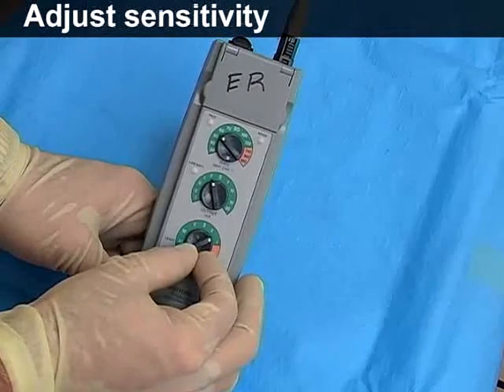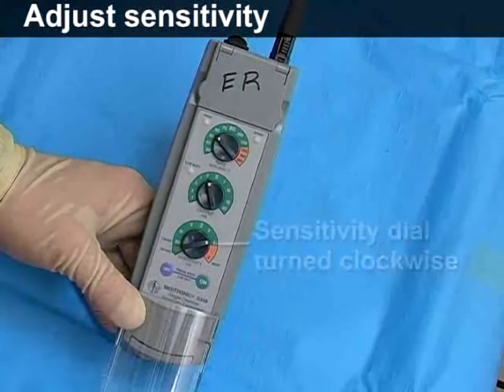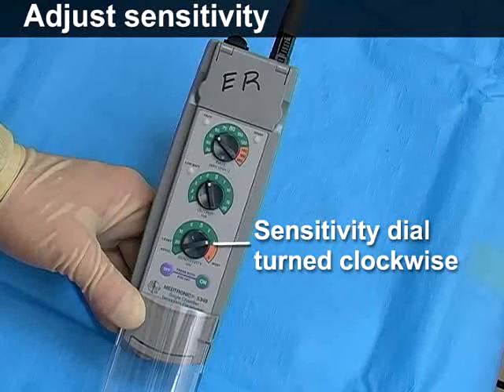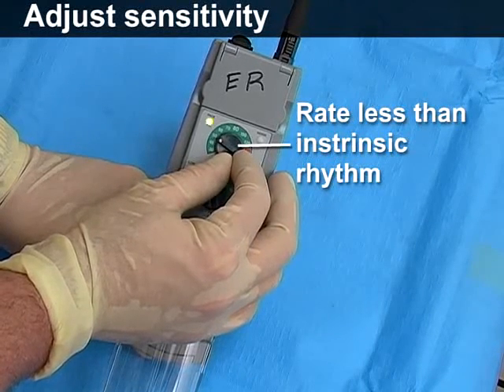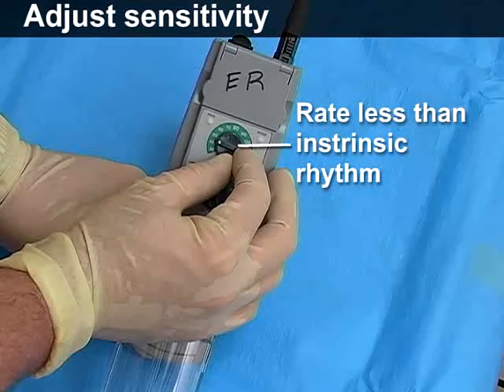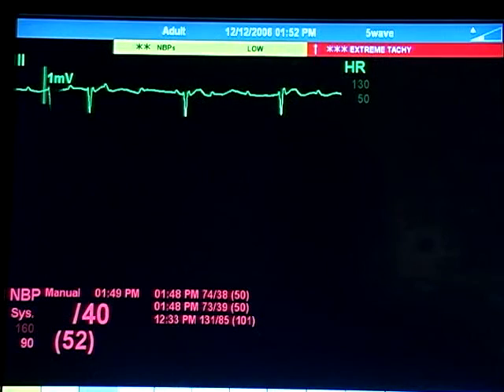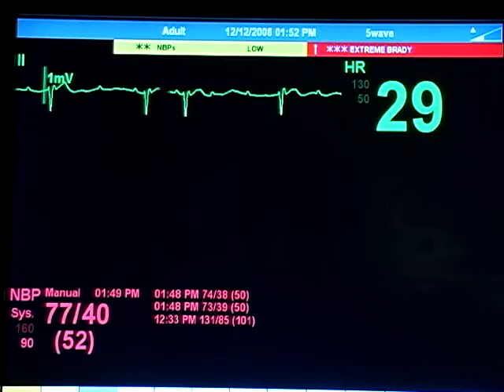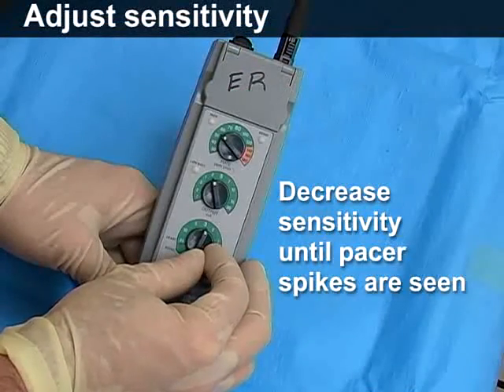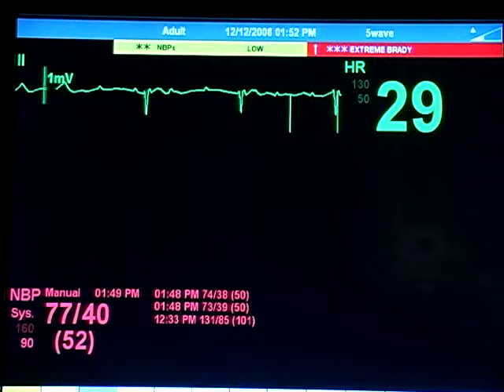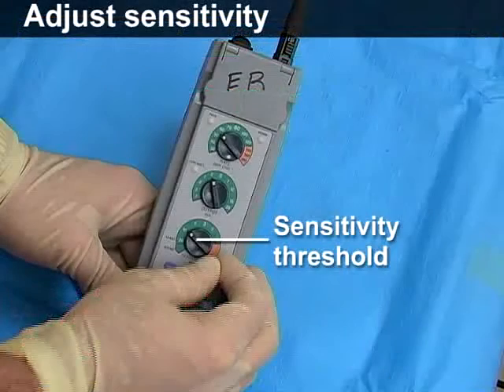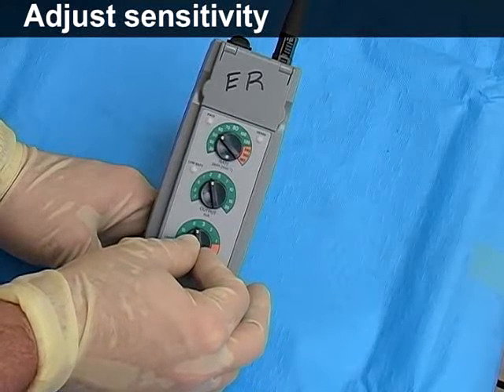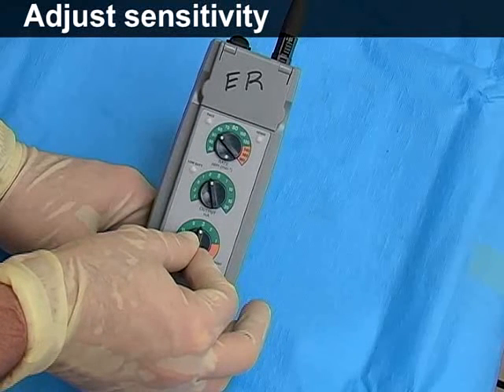Now, adjust the sensitivity. Begin in full demand mode with the dial turned completely clockwise. Reduce the pacing rate to a level 10 beats per minute less than the intrinsic rhythm. With these initial settings, you should not see pacer spikes. Slowly decrease the sensitivity until pacer activity is seen. This is the sensitivity threshold. Set the sensitivity dial to a point halfway between the threshold and the maximum value.